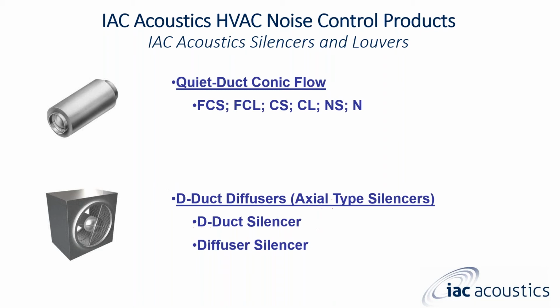The coolest thing about this is that if the fan is operating, say, at 5 static pressure and you really need to knock this down, we can knock it down to about 1/2 inch static pressure. So get with me on this. If there's any need for the D-duct diffusers, we like to do those in-house for engineering purposes, to make sure that these things are designed proportionally.